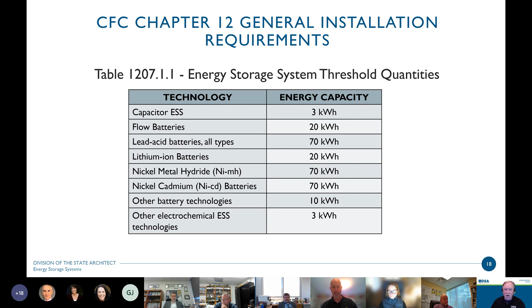So Section 1207.1.3 contains 10 elements that need to be included as part of the construction documents. So designers need to review 1207.1.3 and make sure that their submittal packages at a minimum include these elements. So obviously a site plan as to where the equipment is going to be installed, any details of hourly fire resistance ratings of assemblies enclosing the ESS where it's applicable, and certainly the quantities and the energy capacity and the type of battery technology being used. That's going to be the basis for referring back to the tables in 1207, which are going to then establish the specific requirements necessary for compliance.